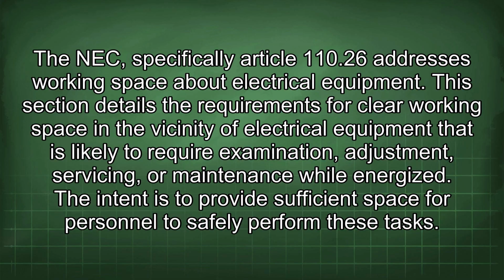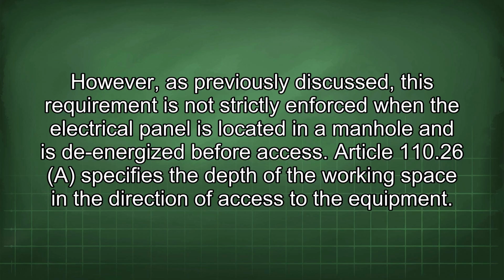The NEC, specifically Article 110.26, addresses working space about electrical equipment. This section details the requirements for clear working space in the vicinity of electrical equipment that is likely to require examination, adjustment, servicing, or maintenance while energized. The intent is to provide sufficient space for personnel to safely perform these tasks. However, as previously discussed, this requirement is not strictly enforced when the electrical panel is located in a manhole and is de-energized before access.